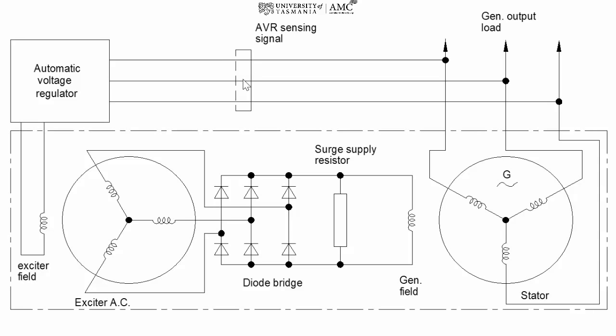senses that voltage through this sensing signal here, goes to the automatic voltage regulator, and this determines the output for our exciter field. So this is controlling the output, which eventually will result in the amount of magnetic field strength from our field coils. So the amount of DC voltage going to our electromagnets in the field coils will then determine the strength of our voltage output, 415 volts. So the AVR controls the output.